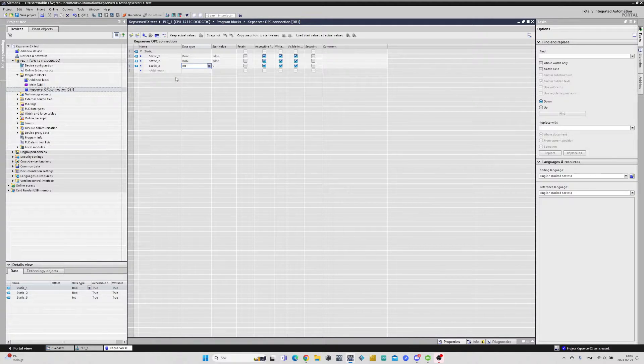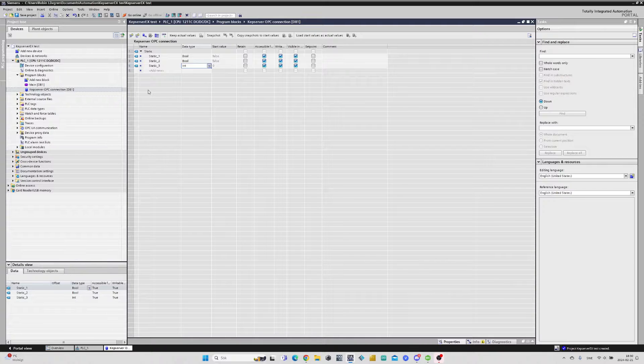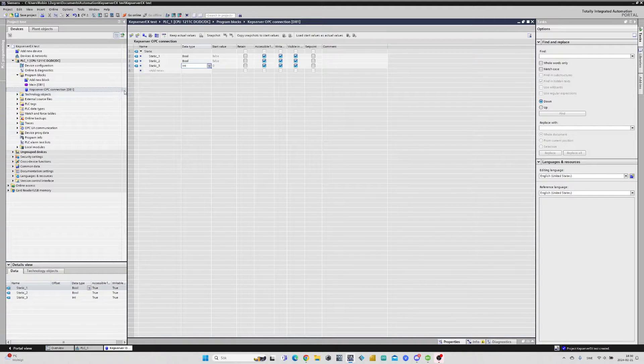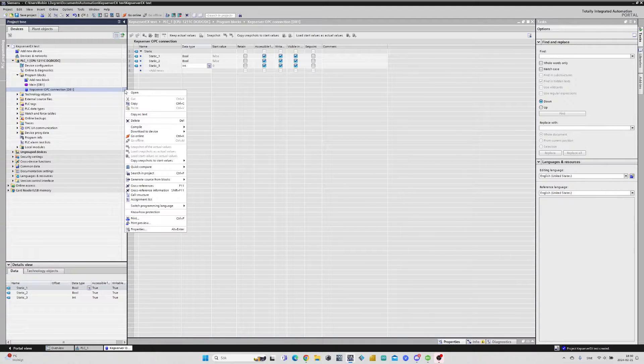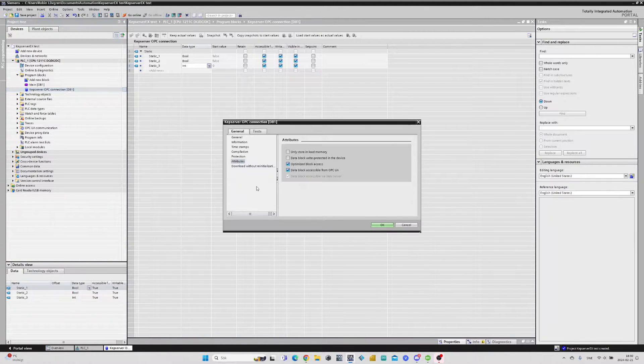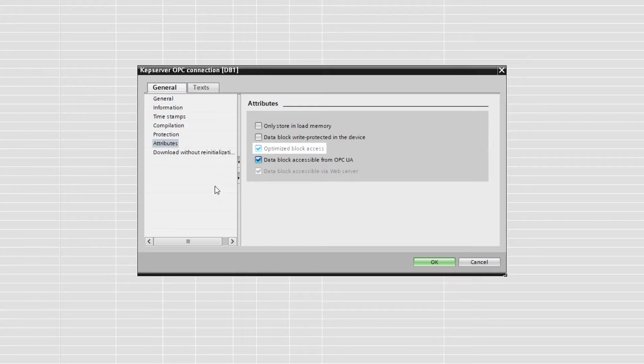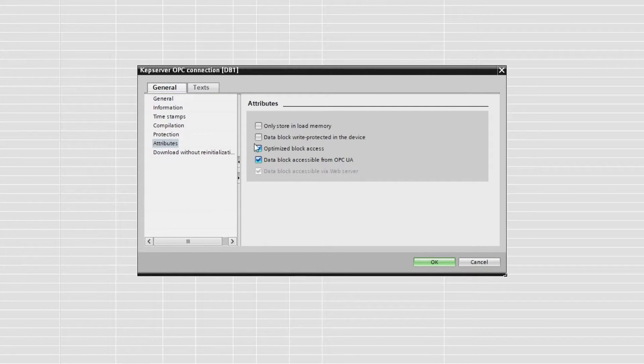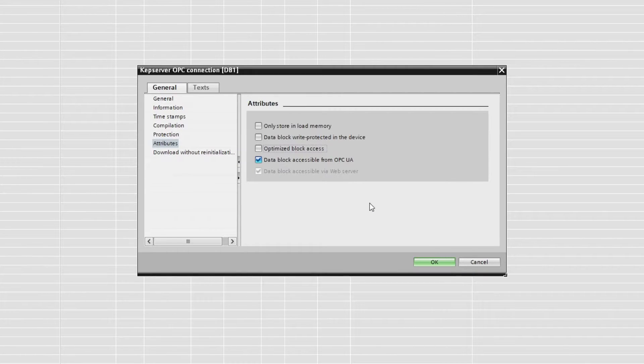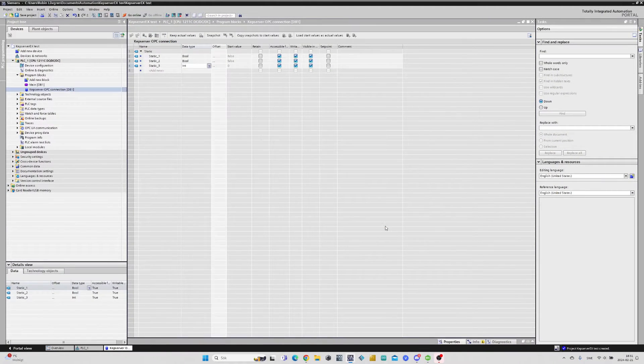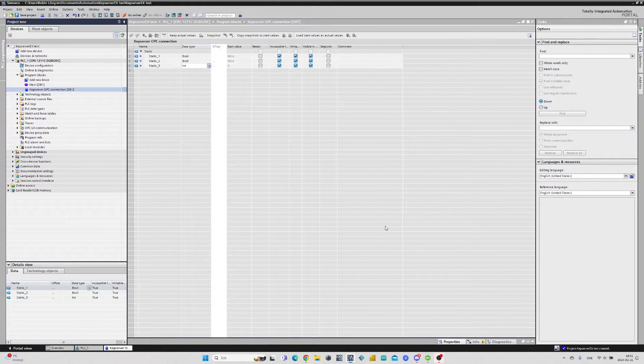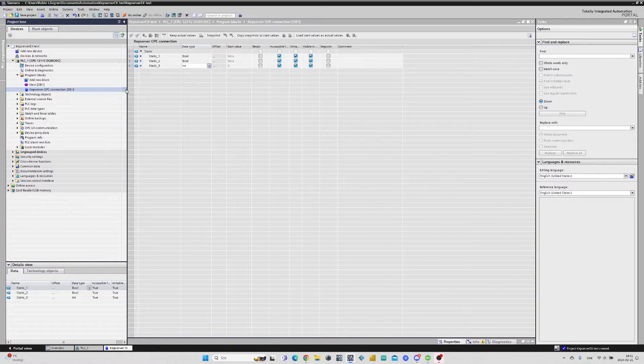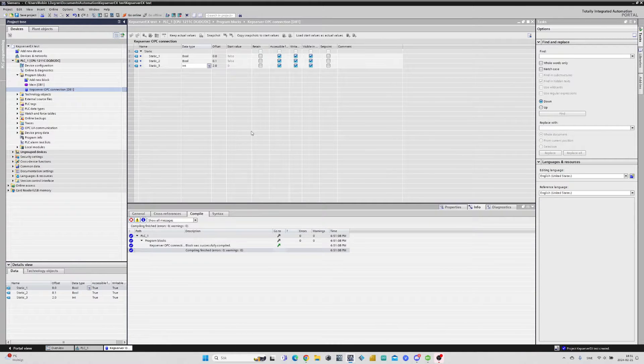To use our tags inside an OPC UA server we will need to address our tags. To address tags inside a data block we have to right click on our data block and then click on properties. Here we will find a checked box where it says optimize block access. This box needs to be unchecked and then we click on OK. Now we will get a new column that is named offset. If we now compile our program we can see that all our tags automatically get addressed in this column.